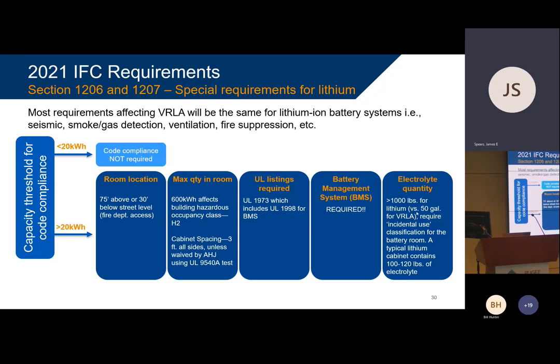Electrolyte quantity, those of you that are battery geeks may know that over the 50-gallon electrolyte limit for valve-regulated lead acid requires incidental use classification for the room, other building code related restrictions. They don't express it in gallons for lithium. They say if you've got more than 1,000 pounds of lithium, you're going to have to set up the room as an incidental use classification. So each of our lithium batteries and the competitors as well, between 100 and 120 pounds of electrolyte per cabinet. So I'd have to have 8 to 10 cabinets to get over 1,000 pounds. So these are the kind of things you want to think about at the design stage.